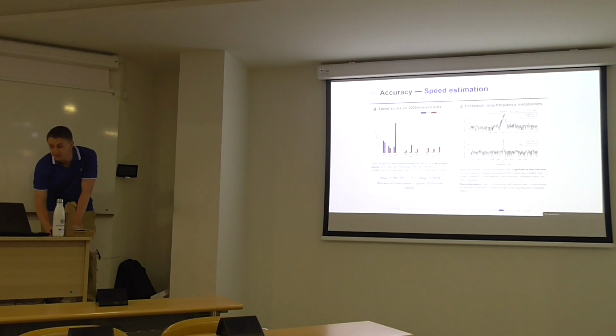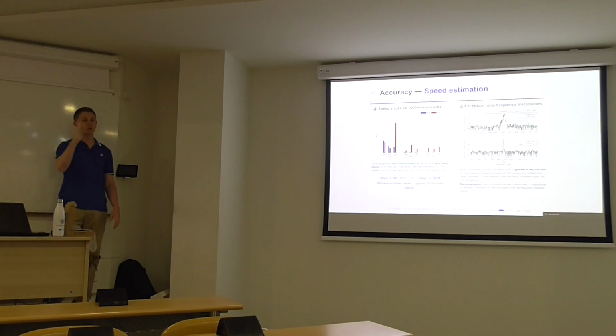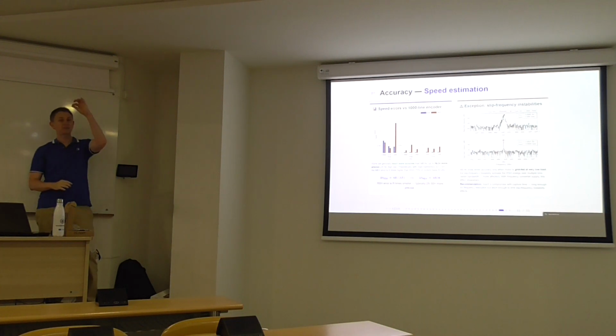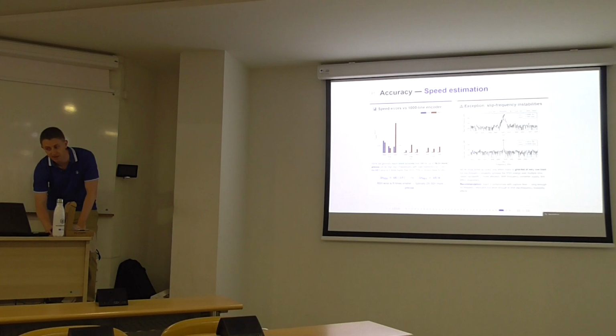Why? Well, in that case, we have a lot of slip frequency instability. That is, the rotor slot harmonic is moving a lot. So the highest peak, which is marked here, does not match the average speed. So there is a big error.